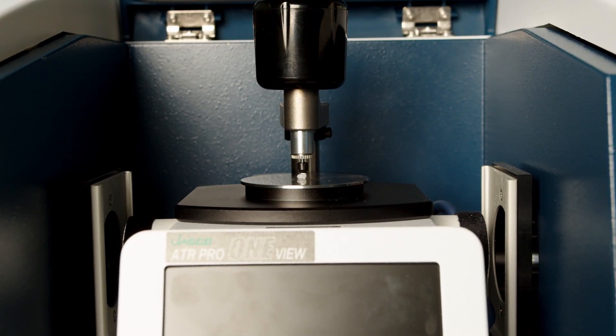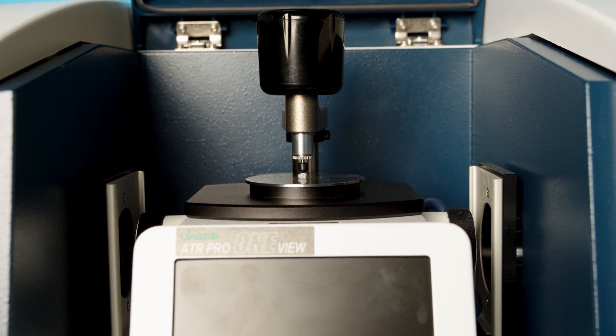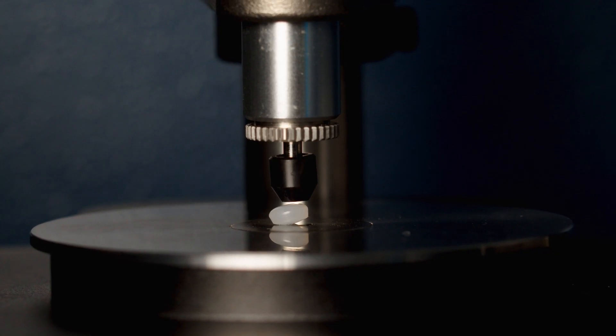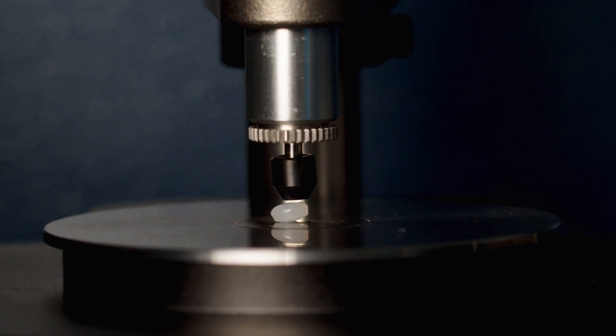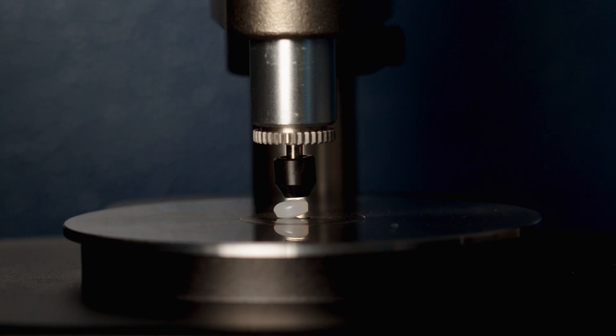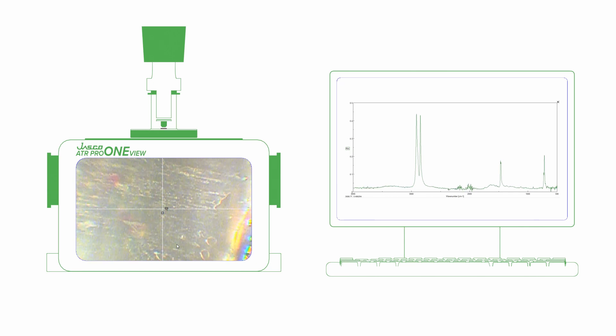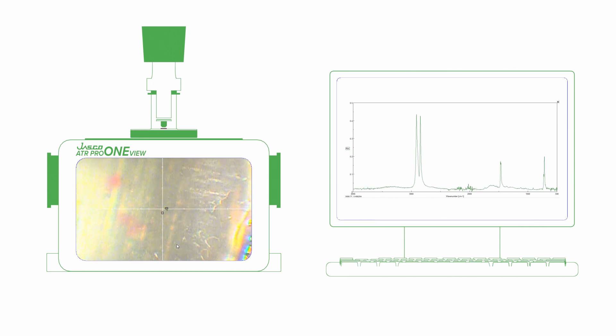Today I'm going to be working with large samples, and for these we have the ATR Pro 1 View — our ATR accessory that has an LCD screen in front and also a digital camera, so it is possible to take images of samples and also collect chemical information. In this photometric method, the sample is in full contact with the ATR crystal.